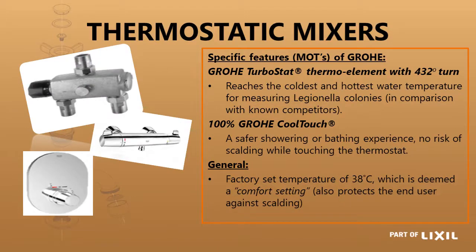The next one we are looking at is thermostatic mixers. The GROHE TurboStat has a very fast reaction time — 0.3 of a second instead of 0.6 as normal — so the reaction time is much faster. It also has a 432-degree turn on the elements so that it takes a nice gradual setting. The mixers also have the GROHE CoolTouch, which means the hot water side of the mixer never gets so hot that you will burn yourself — it should never exceed about 38 degrees Celsius. Your thermostatic mixers normally come factory preset at 38 degrees Celsius. It has a non-hold-open feature so that even if the cold water fails, you will not burn yourself.